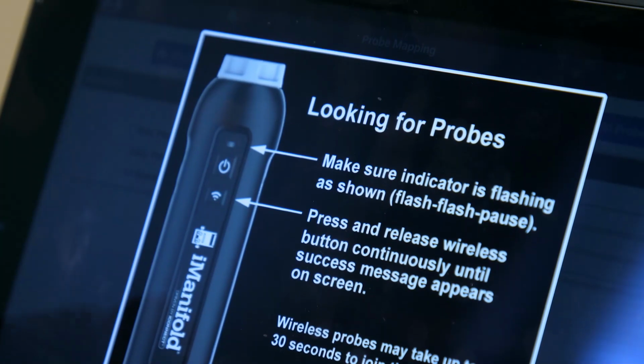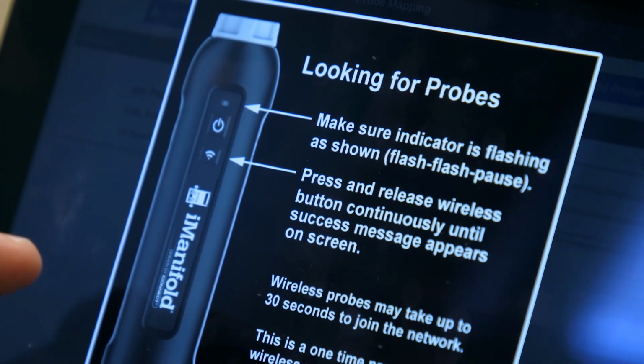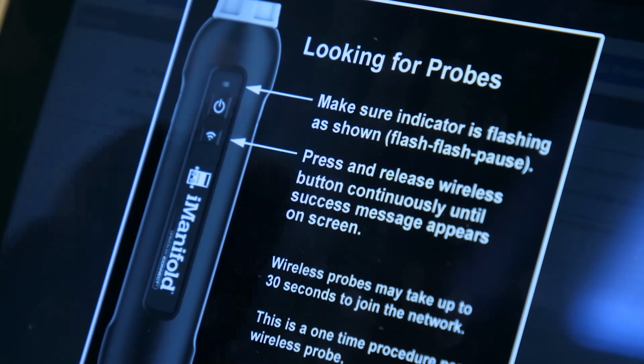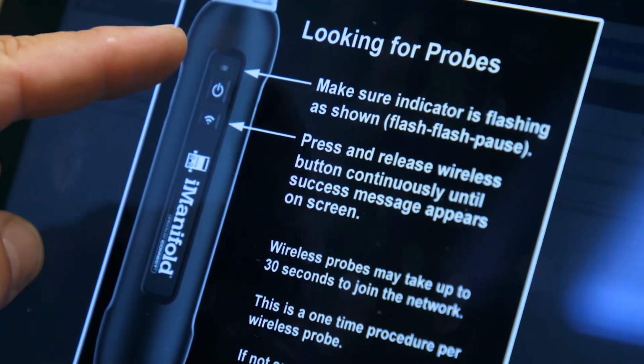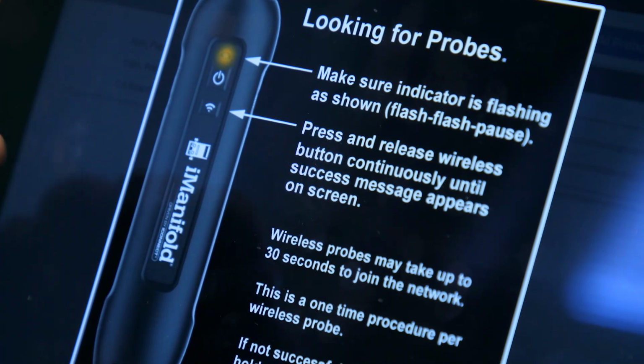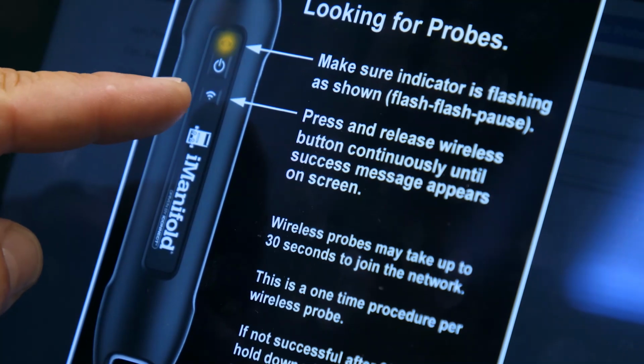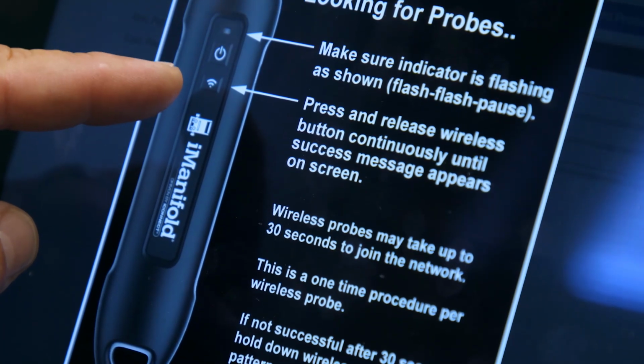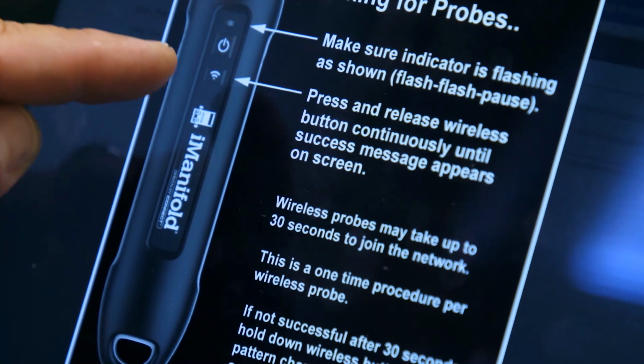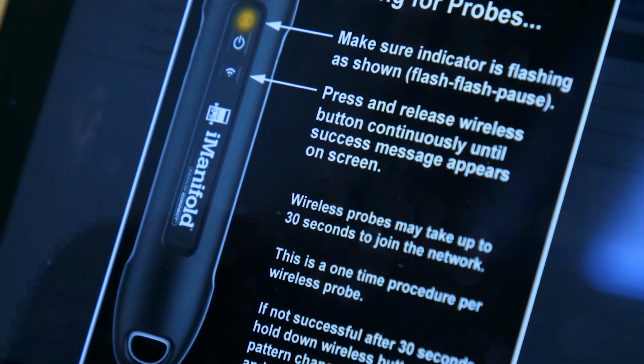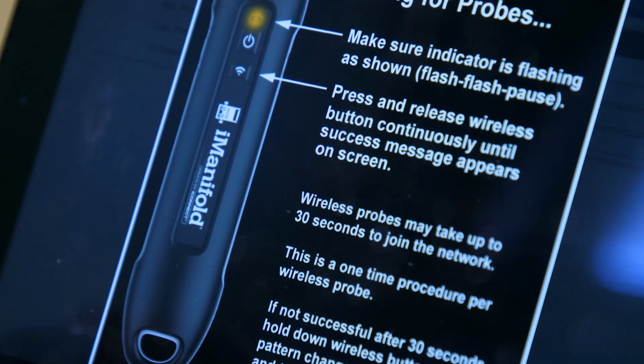Wireless probes may take up to 30 seconds to join the network, so give it a second and be patient. If it starts blinking fast and nothing shows up on your screen, simply press and hold the wireless key down for 5 seconds and repeat. Then press the wireless key briefly again and the probe will show up as paired.